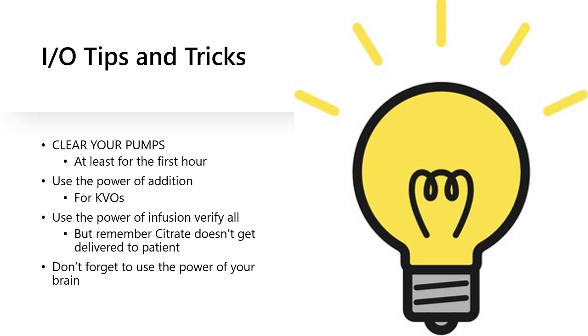possibility of user error. Using the power of infusion verify all can be helpful as long as all of your drips are programmed exactly as such, the way I stated on the previous slide. But remember, citrate does not get delivered to the patient. It should always be marked as 0 mLs. And then we say, don't forget to use the power of your brain. If what Epic is suggesting goes against what you know the patient is receiving, this means that something somewhere is wrong. Either your pump has been programmed incorrectly, or that order in Epic does not match what we're actually doing.